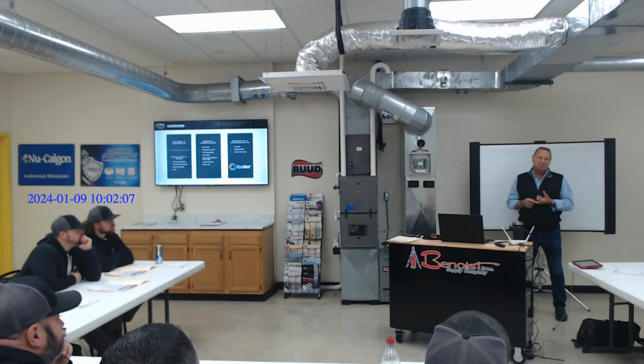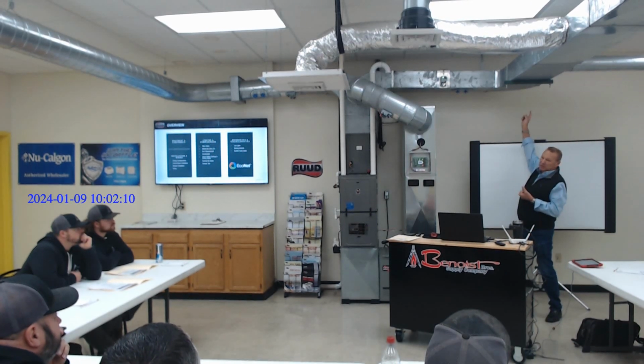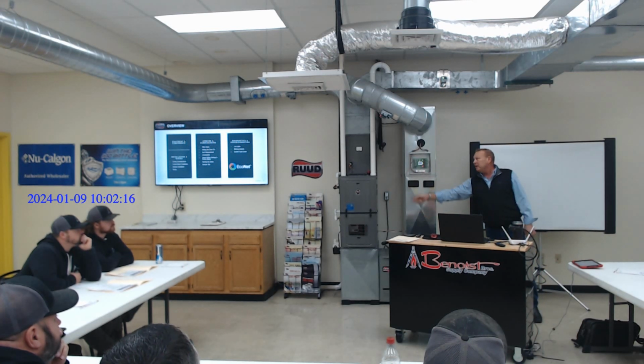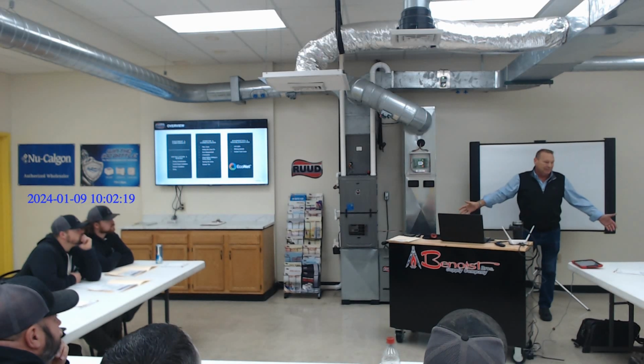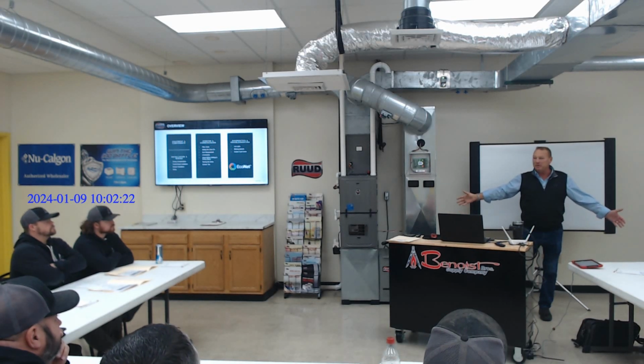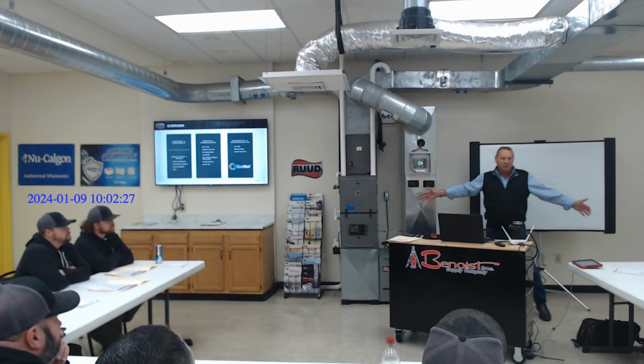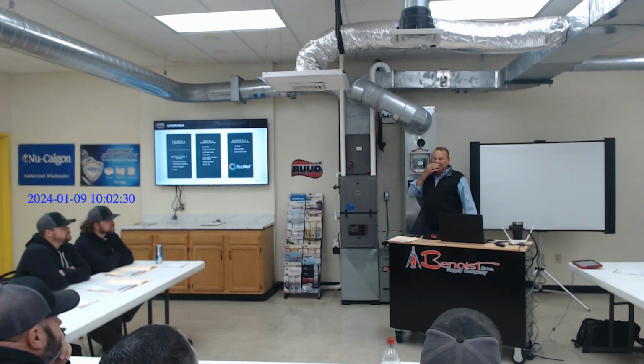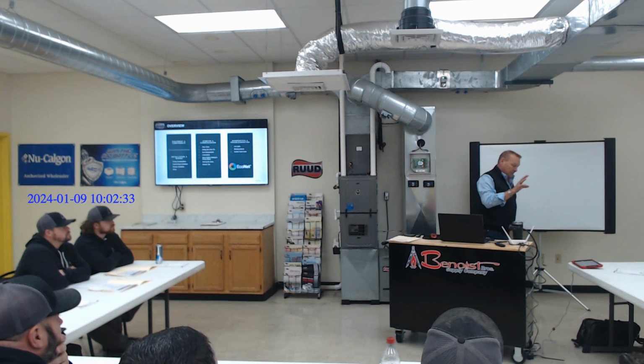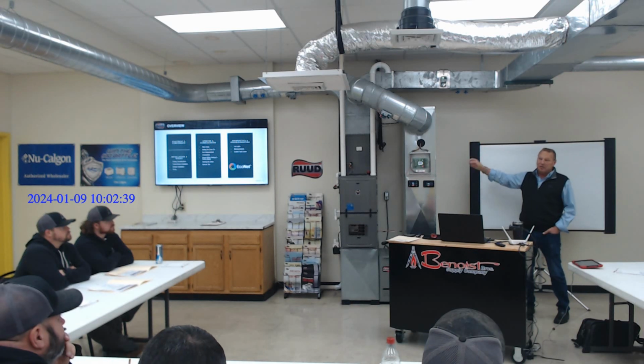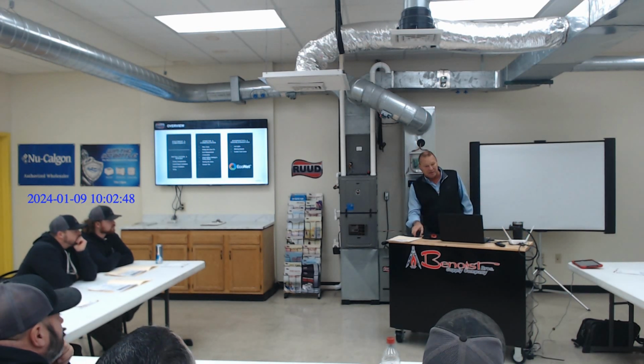Bypasses have always been supposed to be installed down the return line to mix with the air. Probably 70% of the zone systems are tied in right here and right off the plenum, because guess where you're at? You're in a space where they got a full basement, and you got about 20 square feet to work with for ductwork, so you can't do it. You have to do this. That's not at all good for communicating zoning. Because now I've got temperature supply sensor and return sensors in this ECONET zoning that's monitoring the temperature rises to you, okay? So having said all that, we'll get into the zoning.